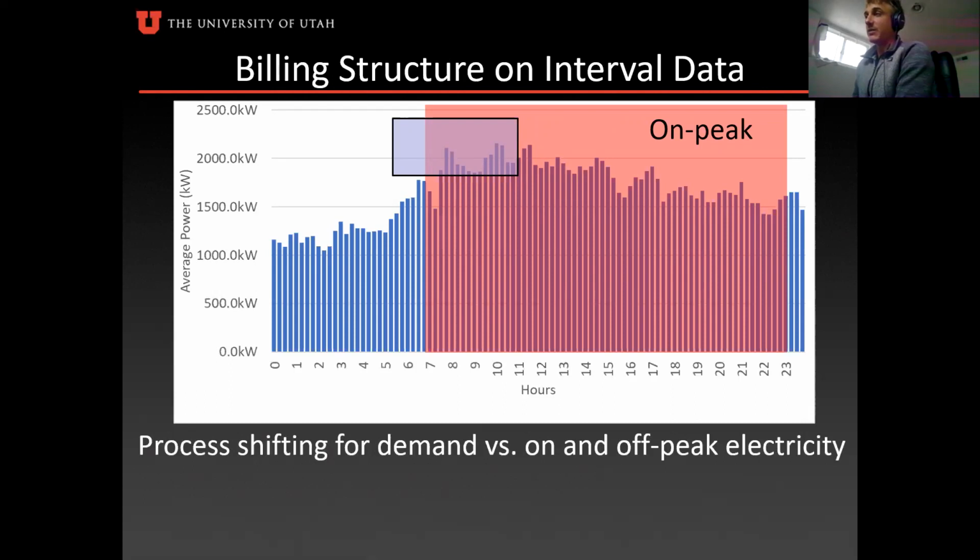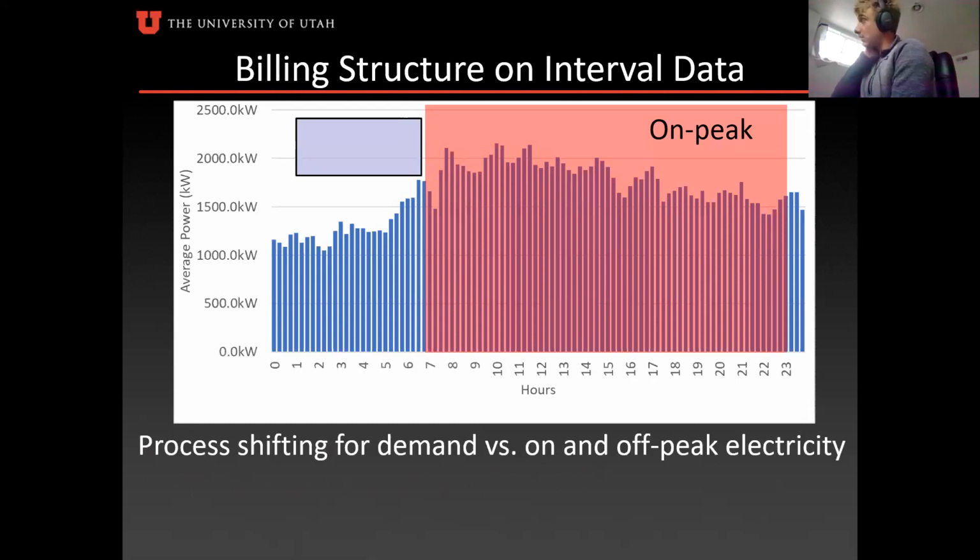It's a little bit more challenging, but with on-peak and off-peak electricity, you can do a partial shift and still see some savings. If 50% or 20% of this process is run during off-peak hours, you just saved a sizable chunk of money if you do that every single day. And then for that partial shift, would it be energy rather than demand savings, just because it's more energy that's off-peak, or is that just okay?